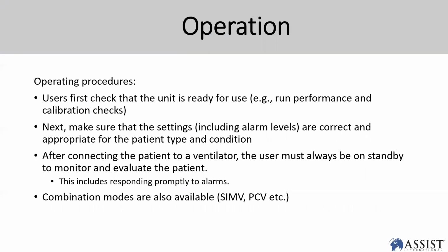So when you talk about operating procedure, you need to do a daily check. Basically, you want to check first whether the unit is ready to use or not. Next, make sure the setting and alarm level are correct and appropriate for the patient condition, all that. That's normally done by the clinician. Then after connection of the patient to the ventilator, they must always check and evaluate the patient. And every single mechanical ventilator used in ICU has different types of modes that you need to know to a certain extent, for you to check in future.